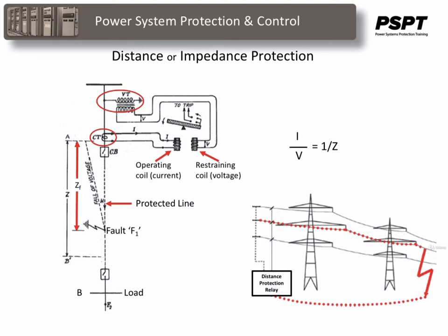The protected zone is not exact, but it is good enough to provide adequate high-speed protection, especially when combined with multiple zones and high-speed end-to-end communication signaling. One of the problems with this simplistic setup is that the relay does not know what direction the current is flowing. It operates solely on the magnitude of the current and will operate for faults in the opposite direction, looking back into the bus.